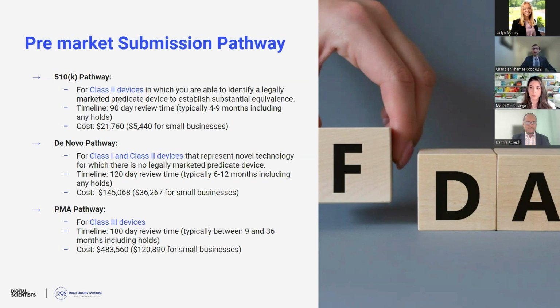In the event that your device would be a Class 3 device, the timeline officially is 180 days, so up to 6 months, but really this can go anywhere from 9 to 36 months, including holds. The reason for that extensive timeline delay might be FDA requesting additional clinical studies, the manufacturing site inspection and audit, as well as a couple of other things as part of that more intensive review for formal approval. And because of these things, the cost also skyrockets up to $483,560. And with a small business designation, that drops to $120,890.